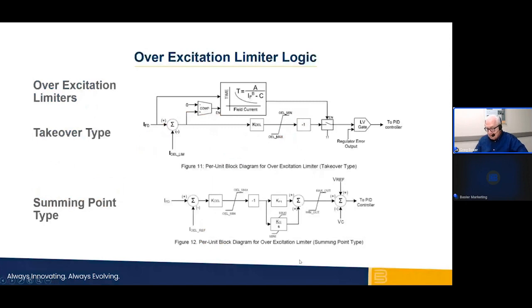The purpose of the overexcitation limiter, OEL, is to ensure that the thermal capability of the rotor's field circuit windings is not exceeded, while the automatic voltage regulator is in control. The machine's nameplate will include a rating of the field current required at full load, rated frequency, rated voltage, and rated power factor. That value is fundamental for establishing the limits for continuous field current for the machine. The machine builder's field current rating corresponds to the heat dissipated in the rotor windings, the built-in cooling support, and the physical limits of the insulation system for these conditions of the conductors. These limits are implicit in the nameplate rating with considerations for safety margins.